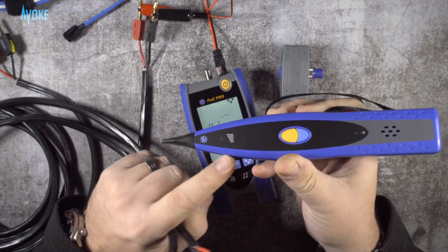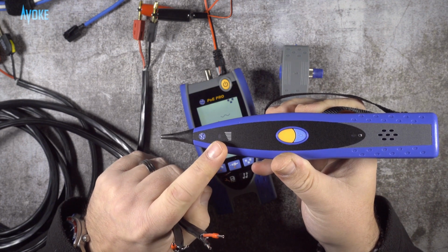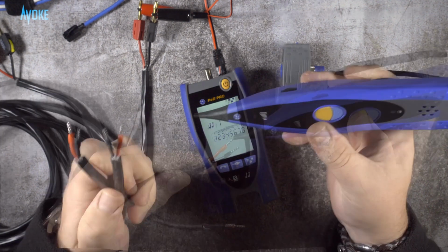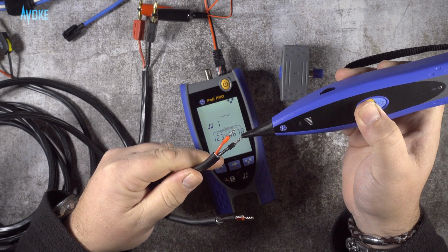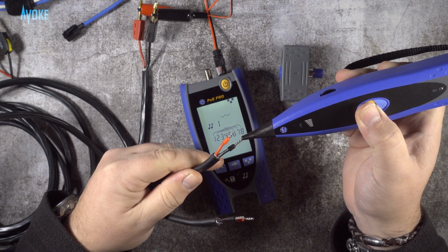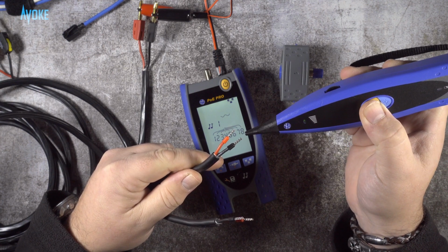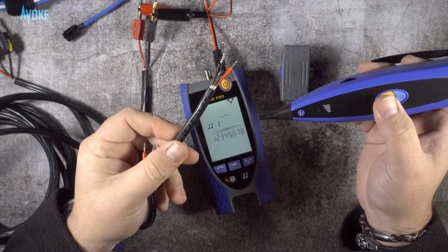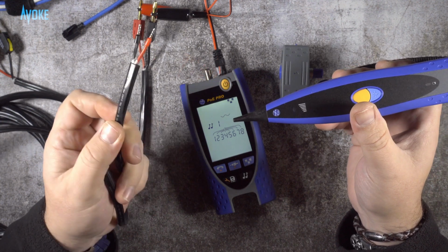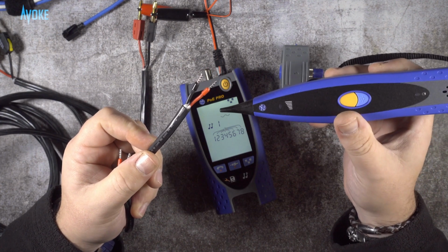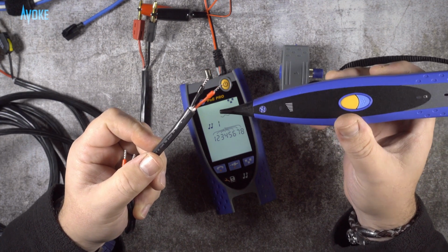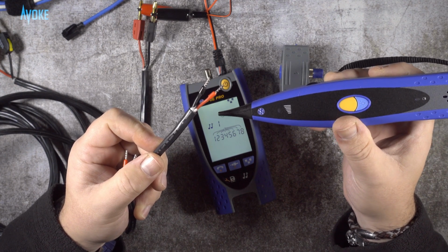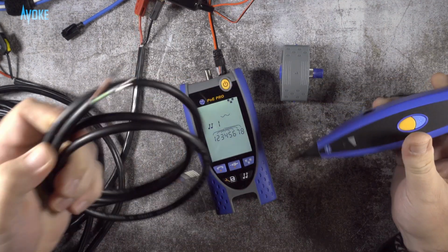And what's also really cool is you've got a confirmation light as well as the volume increase. There we go. The other conductor is picking it up just a touch, but that would be crosstalk because the cables are coiled up. But that's a definite. And then you can label that cable up. And if you've got anything more than a pair of cables, then this is going to save you time on every single site and where you've had no control over what's happened previously, even as far as power cables.